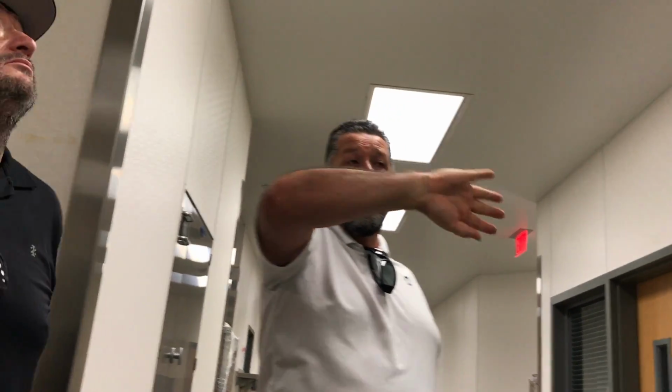Plus, new buildings are required to have fire sprinklers throughout. So it's a 100% sprinkler building, and up in all the duct systems and everything, it has the ability to shut down the ducts to contain fire within areas. So right across that wall, every duct that penetrates there has a fire damper. When we initiate this alarm, all those dampers shut.